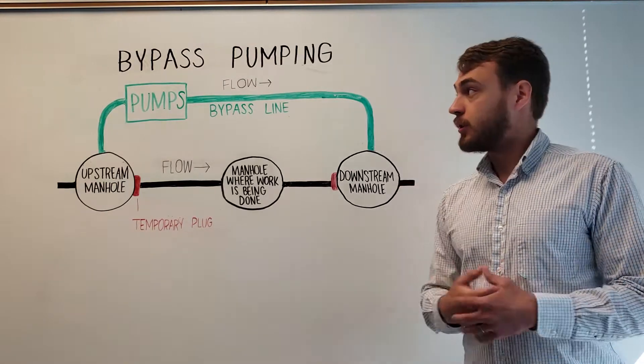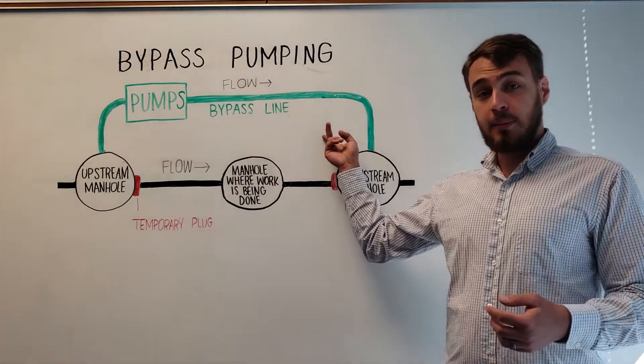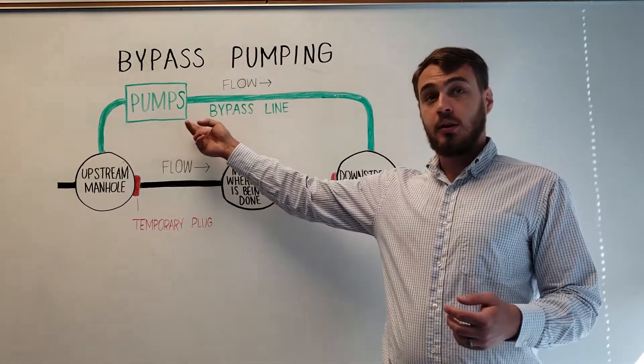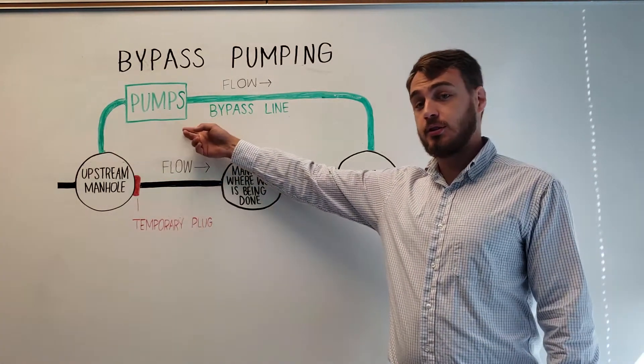So there are some key considerations when you're doing a bypass pumping plan. The first thing is the length of your bypass pump lines, the location of your pumps and your expected flows must be known in order to properly size your pumps and your bypass lines.